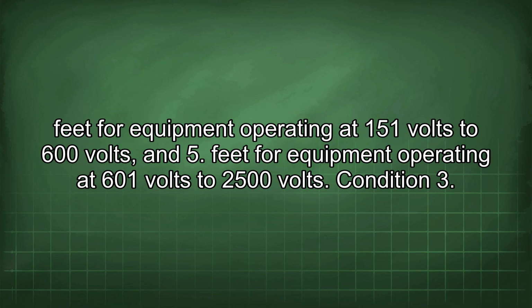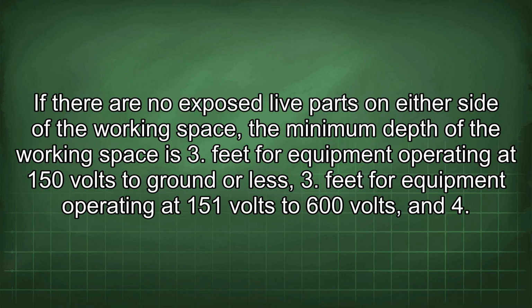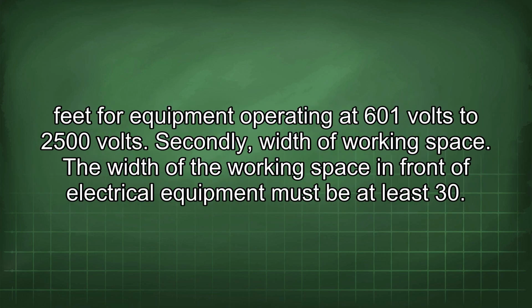Condition 3. If there are no exposed live parts on either side of the working space, the minimum depth of the working space is 3 feet for equipment operating at 150 volts to ground or less, 3 feet for equipment operating at 151 volts to 600 volts, and 4 feet for equipment operating at 601 volts to 2500 volts.